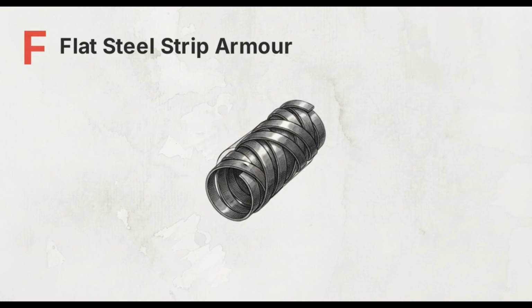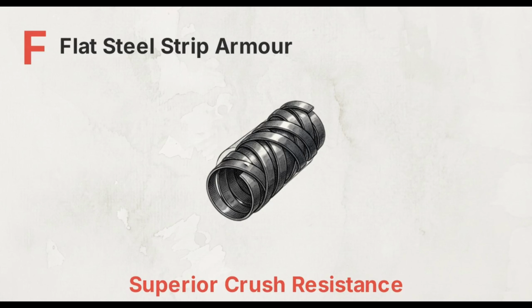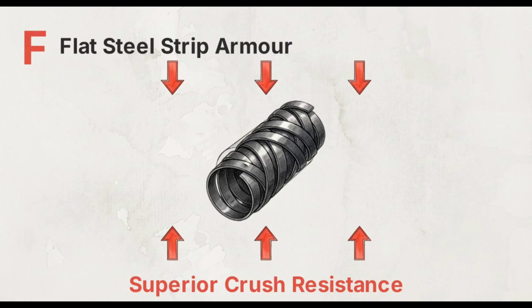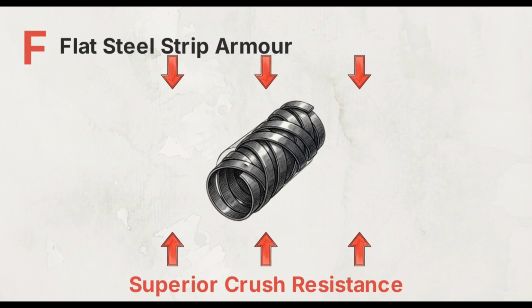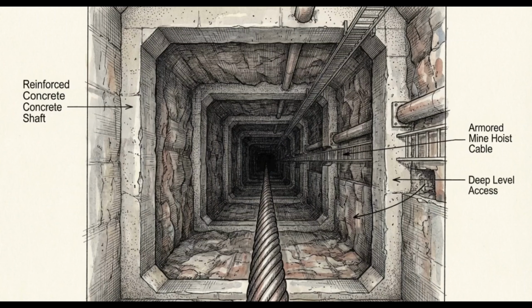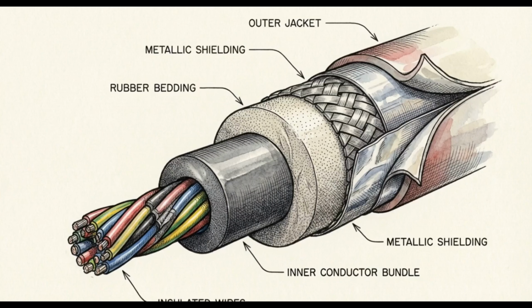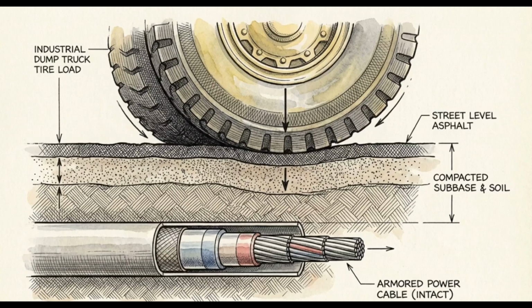The letter F identifies the flat steel strip armor, the layer responsible for physical defense in severe environments. Flat metallic tapes provide the high crush resistance needed for direct bury applications, where the cable must survive heavy terrestrial pressure. This differs from steel wire armor, which utilizes galvanized round wires to achieve entirely different mechanical properties. Wire armor is specified for vertical suspended runs or areas prone to ground movement, where high tensile strength prevents the cable from being pulled apart. Before these armors are applied, an extruded bedding layer binds the multi-core assembly together, creating a stable circular foundation for the metallic wrap. Armor topology forces the electrotechnical design to withstand civil engineering loads without compromising the internal electrical flow.